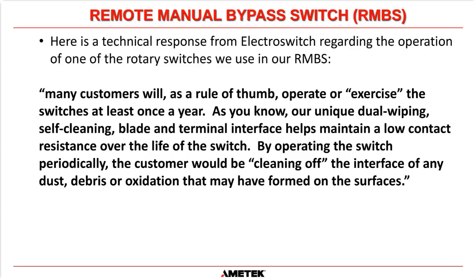That is why we always recommend that when you have an annual PM performed on your UPS, one of the things that you must do is move the RMBS, the remote manual bypass switch, and clean those contacts. Okay, I know some people get nervous about moving an RMBS, but if you're doing it on an annual basis, you should never have any issues.